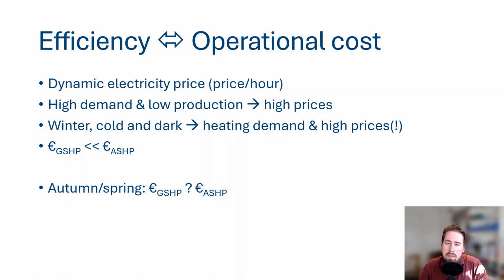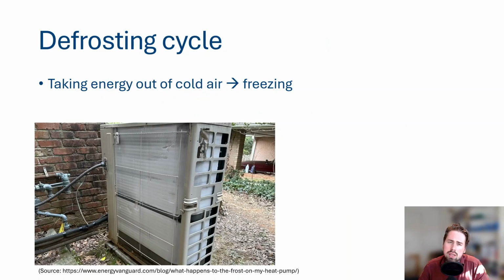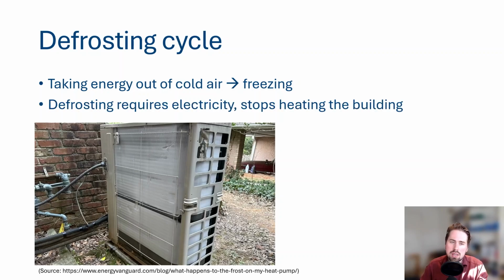Next to that, air source heat pumps also experience something called the defrosting cycle. Now, an air source heat pump takes the energy out of the air. There is moisture in the air, and if it's cold outside and you extract the energy from the air, it cools down and the moisture can freeze. It freezes on your heat exchanger, and when there is ice there, it cannot function anymore. So that's why there is a defrosting cycle with these types of systems. But these defrosting cycles require electricity.